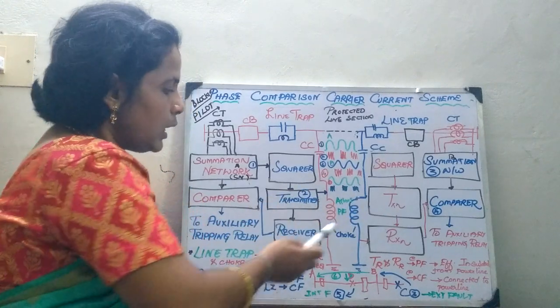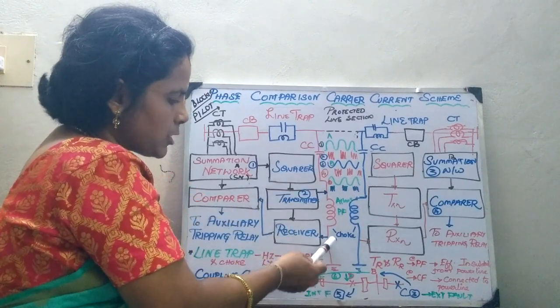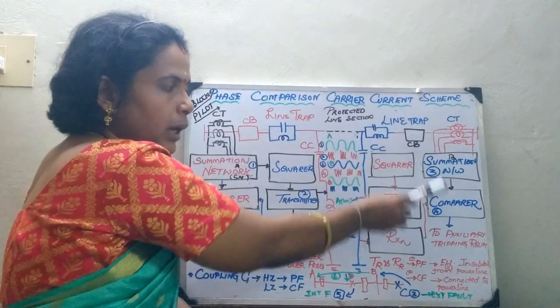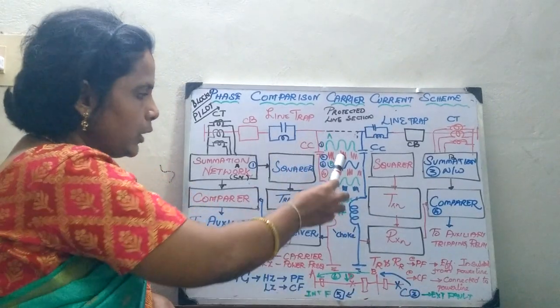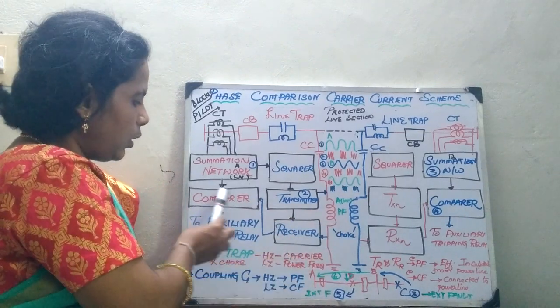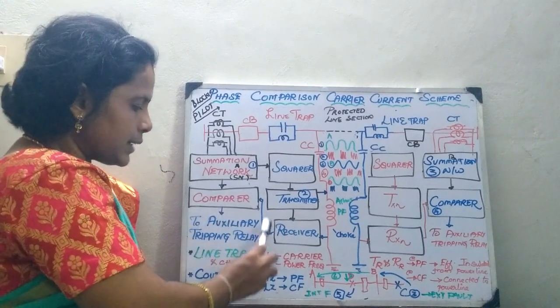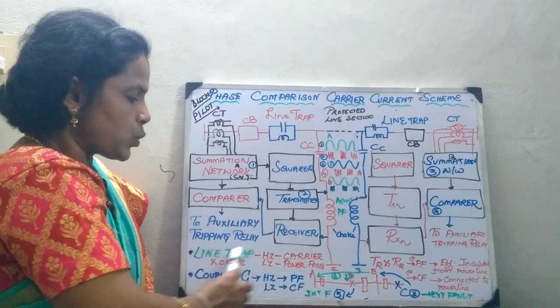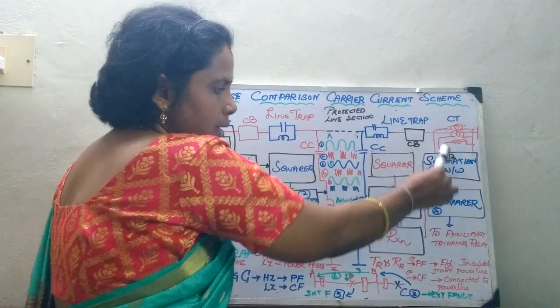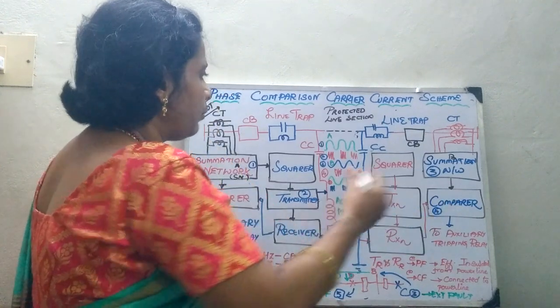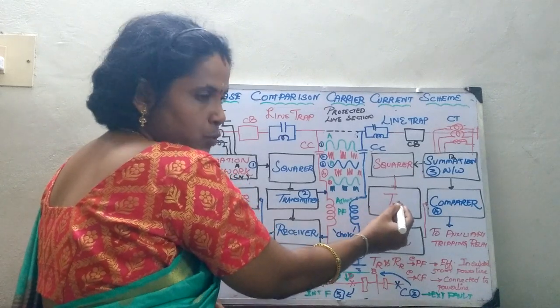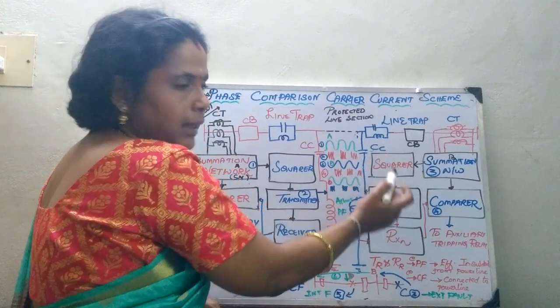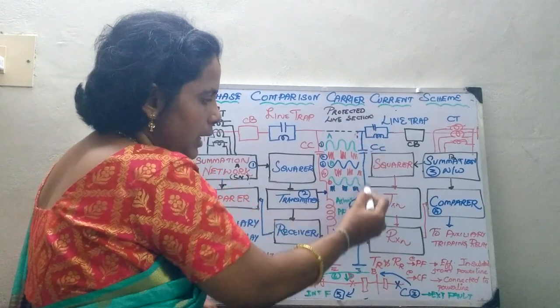On the other side, after the signal is transmitted, the received signal passes through the line and through the receiver, where you compare it with the comparator. You transmit to the coupling capacitor and derive it through the choke to the receiver, comparing the incoming and outgoing signals. The relay operates whenever the carrier signal is absent. The summation transformer output is given to a squarer circuit, which goes to the transmitter, then through the coupling capacitor and choke to the receiver.